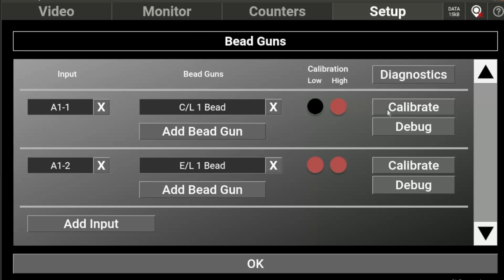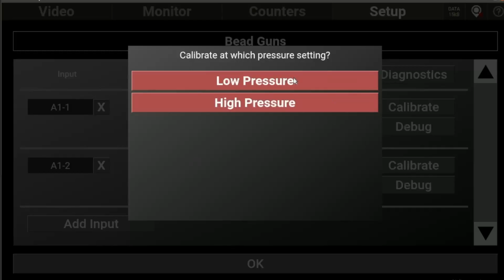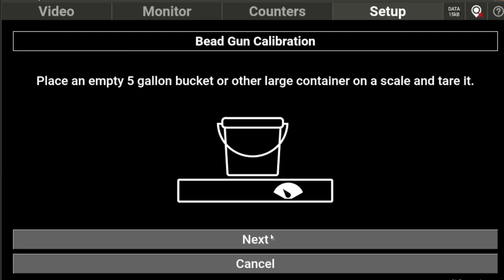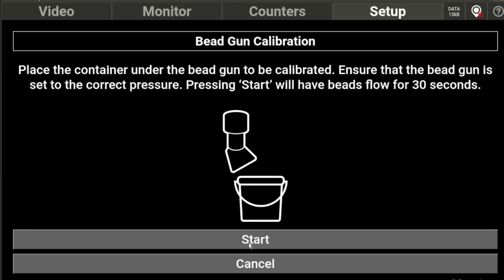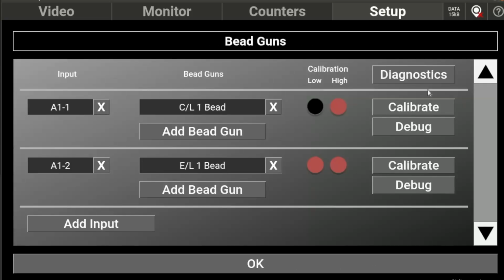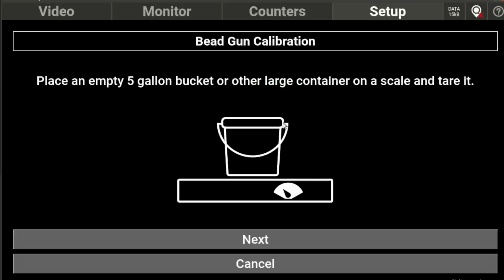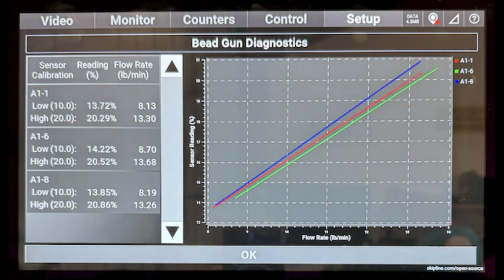Repeat this process for each bead gun, using the same pressure setting for consistency. Once all guns are calibrated at the low pressure, repeat the steps again for your high pressure setting. When calibration is complete, check the Diagnostics tab. You should see a clear incline from left to right for each sensor, indicating more flow at higher pressures. If the line looks flat, jagged, or illogical, recheck your calibration.